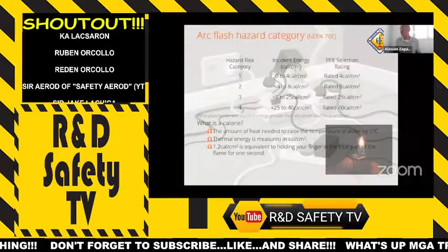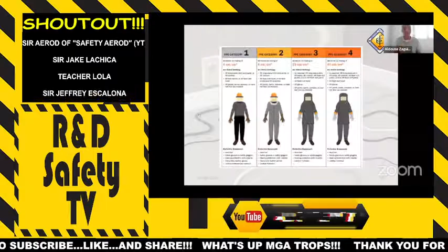Okay? And these are the types of PPEs in accordance with these categories. Up to the one that really looks like an astronaut, the technician with all the insulation for thermal shock protection, which is on the hands, the rubber gloves, the leather protector, and on the footwear, the electric shoe. Okay? Rated depending on the voltage of the equipment being handled, up to 20,000 volts. Okay? So there's that shoe.